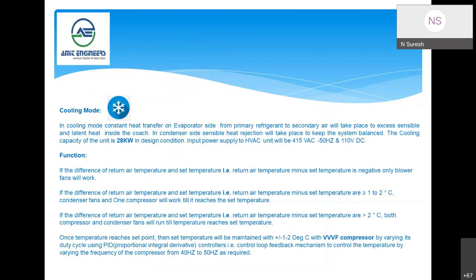Basically, there is a cooling mode. How is it going to work? In cooling mode, there is a set temperature. To meet the set temperature, the microprocessor controller will allow the compressors to work until the set temperature is reached, so that the comfort temperature of 25 degrees is maintained inside.